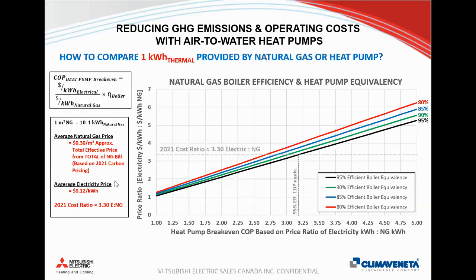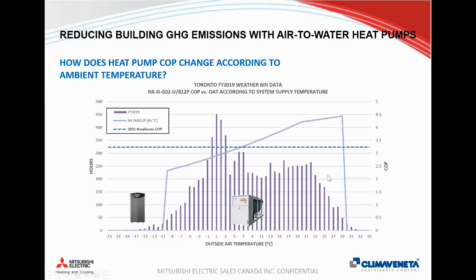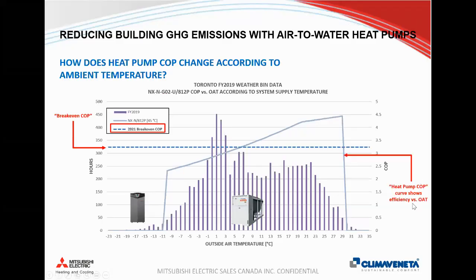But basically, this means that if we're comparing it to a 95% efficient boiler, we basically need a COP of 3.2 in order to be cost neutral. But if we're comparing that to an 80% efficient boiler, really we need a COP only of about 2.6 in order to break even. So now how do we compare that to the COP from the heat pump? Well, this is again using the same rates and figuring out that this break-even COP for 2021 is around 3.3. And this is plotted on the right side of the graph.